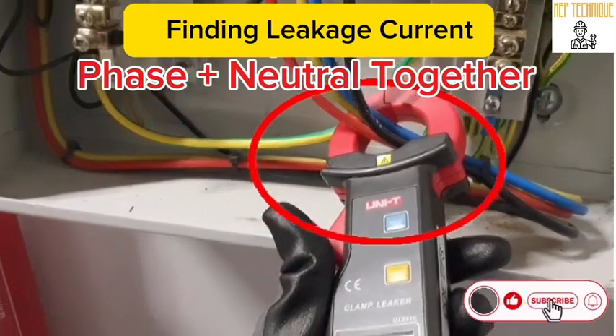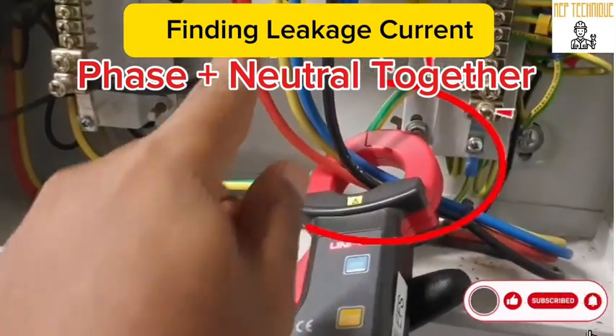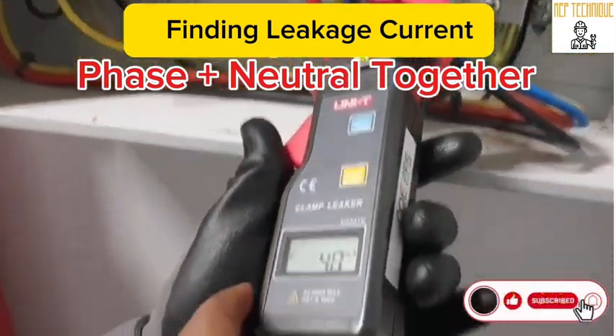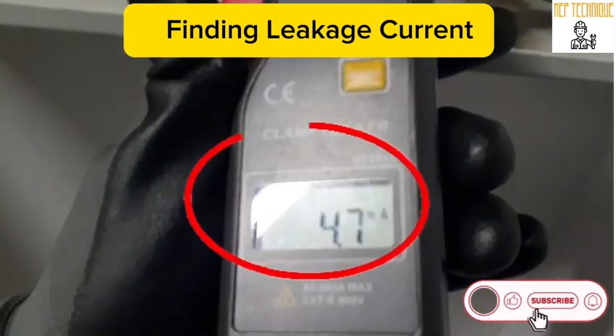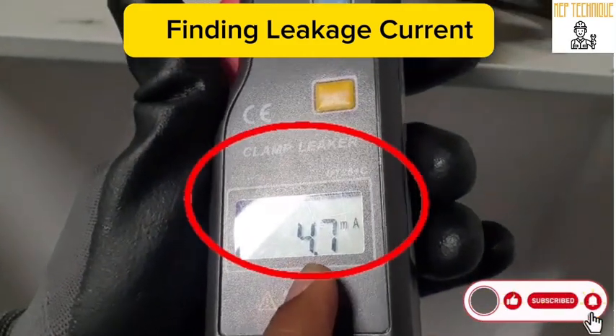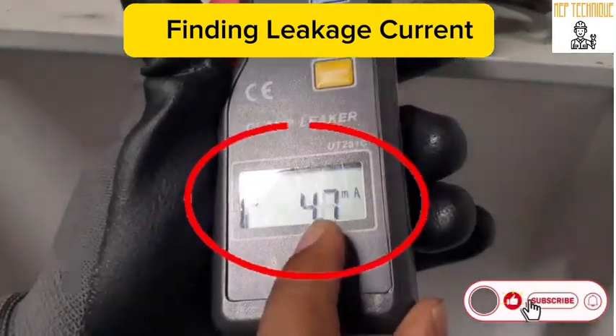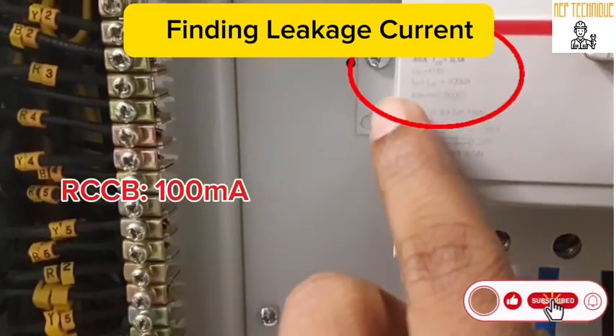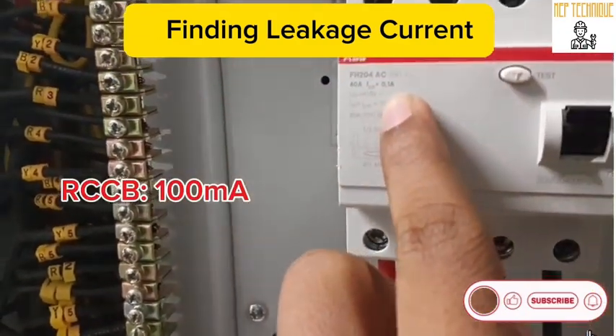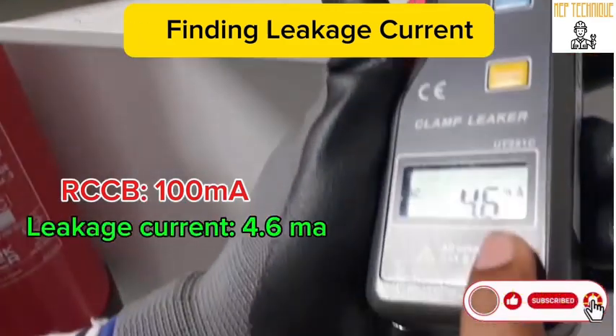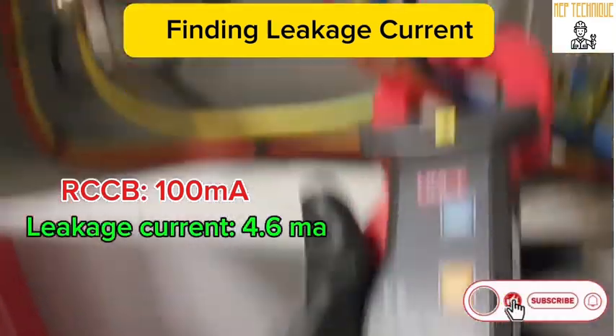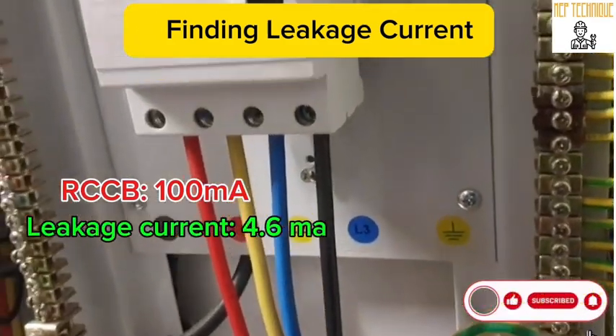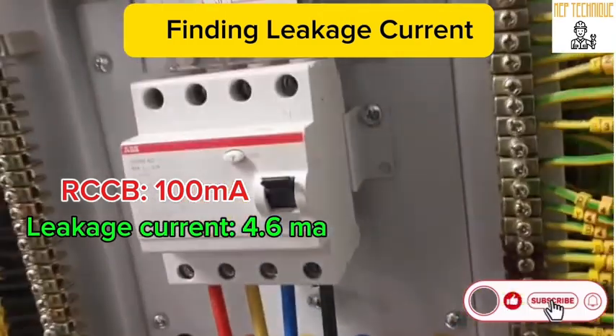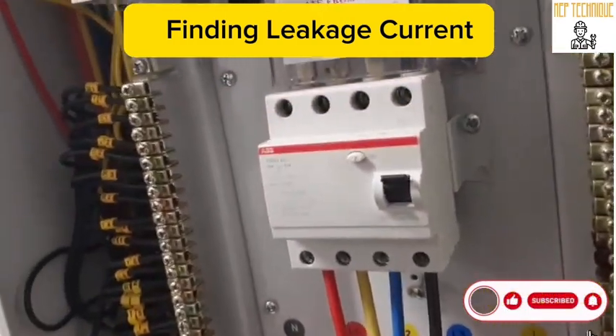We have placed the clamp leaker around all the cables, phase and neutral together, and we can see the reading shows 4.6 or 4.8 milliampere. This is the leakage current currently with this RCCB, which is a 100 milliampere RCCB. The leakage shows 4.6 milliampere, meaning the leakage current is not abnormal, it is acceptable.